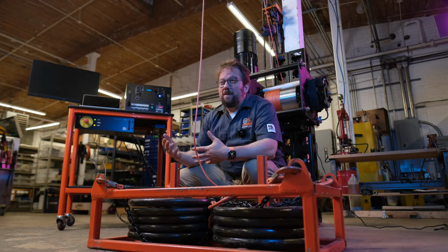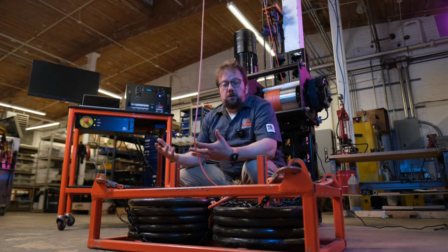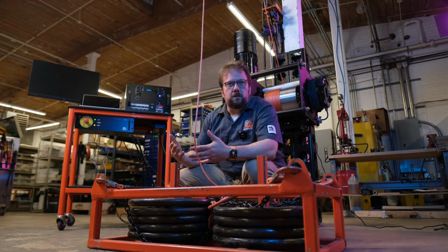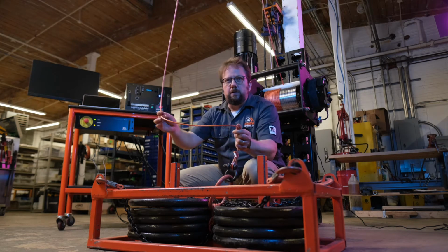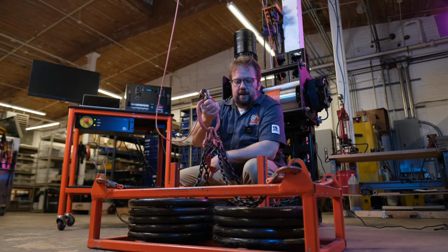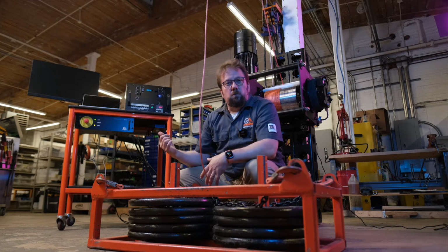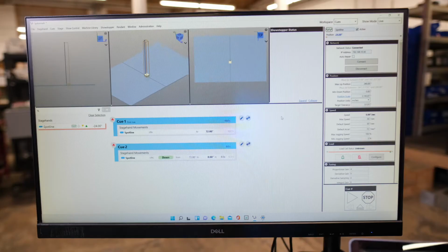Encoders get set by operators. Automation operators set the position. And encoders can fail. So when that happens, we need something else more primitive to make sure that we haven't created a dangerous situation on stage. As a great example, here, like a dummy, I have unwound my hoist too far. This is all slack now, and it's just piled up on the floor. As an idiot, I'm going to go ahead and re-zero the hoist and say this is 0, when 0 should really be off the floor. The hoist is on the ground, and I'm going to go up and reset position to 0.